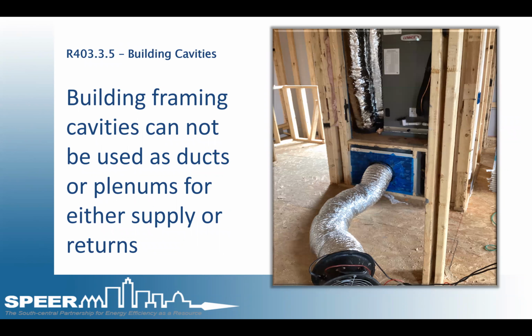R403.3.5, building cavities. These include wall cavities, floor cavities, including floor cavities over conditioned space, return boxes like you see here. I've seen these plenum platforms, these return platforms, these return boxes being passed every day, and no one makes a comment about these not meeting code. In order to be compliant, they really should be lined with ductboard, including the bottom of the floor. All joints and seams be sealed with UL 181 tape or mastic.